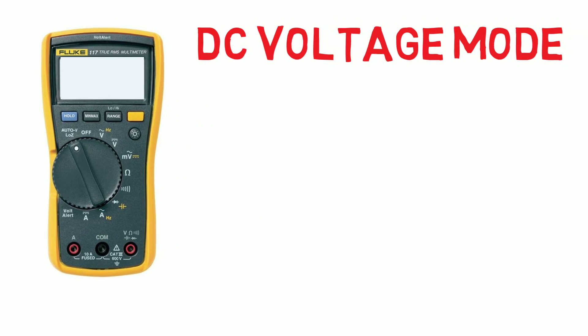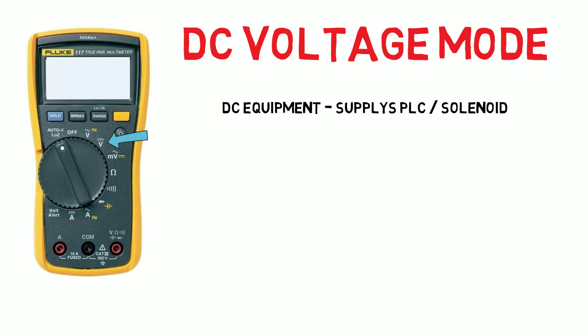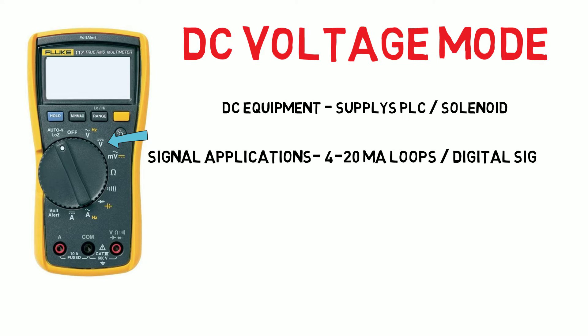This mode is for measuring DC or direct current voltage. Notice there is no hertz function available in this mode, because DC has no frequency as the current continually flows in a single direction. Some equipment may be powered by DC voltages such as PLC equipment or solenoid supplies, especially if battery powered, but they are also found in signal applications such as the voltage in a 4 to 20 milliamp transmitter loop for analog signals and in digital signals where equipment is looking for voltage to be present or not to determine an input state. Common DC voltages we may be testing for are 5, 12, 24 and 110 volts DC.